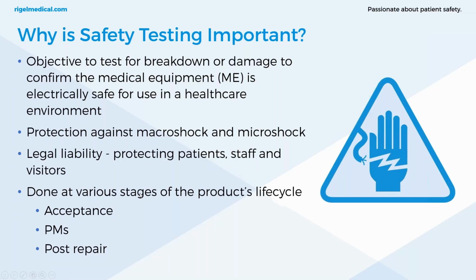And electrical safety is done at various stages in the product's life cycle. There's acceptance. Most medical electrical equipment is designed and developed against the 60601 standard for the strict rules of the design of medical devices. We know that the primary safety process is just to prevent any patient or operator from being exposed to those currents. So an acceptance test is just to ensure that it's as it was when it left the facility.